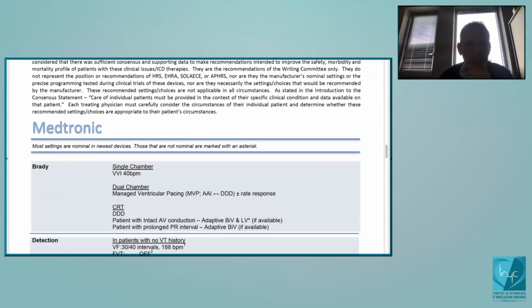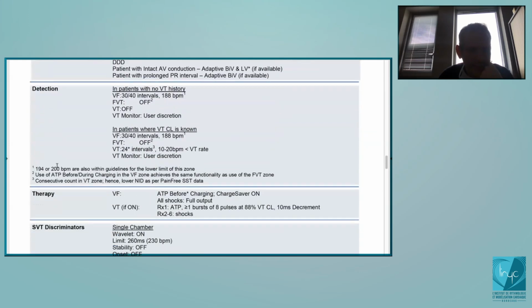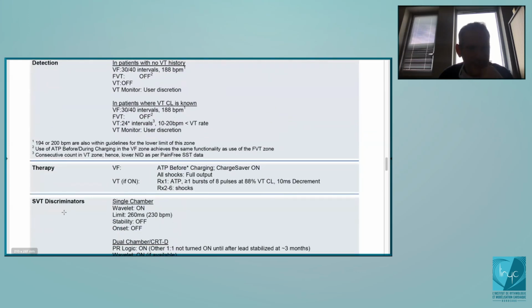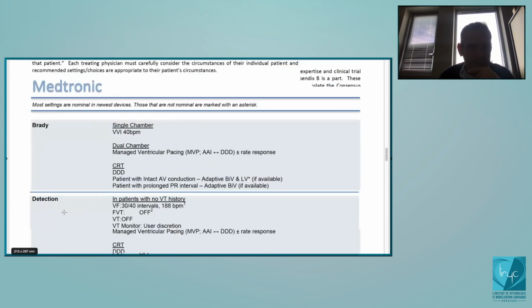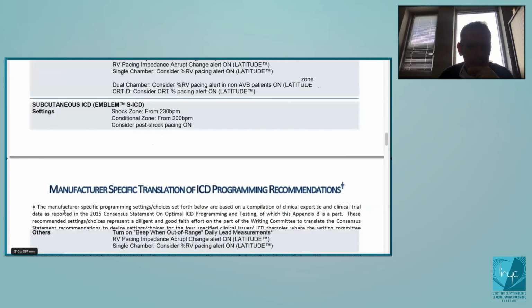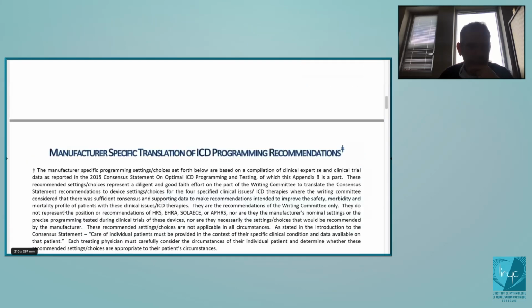So here, what you see is what is recommended for Medtronic ICDs, in terms of brady, in terms of detection, in terms of therapies, and in terms of SVT discriminators. Of course, in the same manuscript, you have the same for, for example, Boston Scientific.